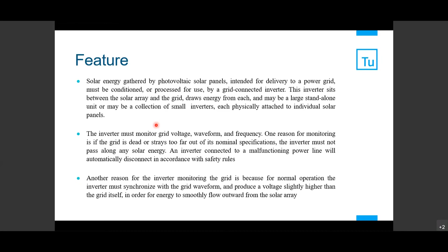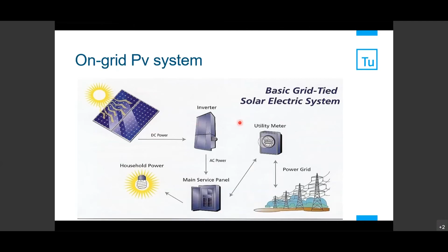Another reason for the inverter monitoring the grid is that for normal operation, the inverter must synchronize with the grid waveform and produce a voltage slightly higher than the grid itself in order for energy to flow smoothly outward from the solar array. And all this should be done by the inverter.